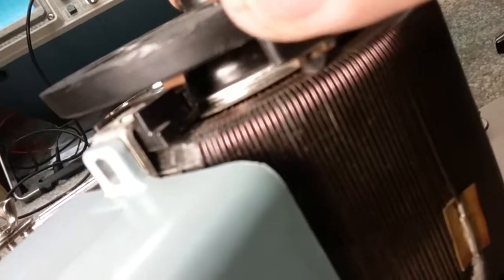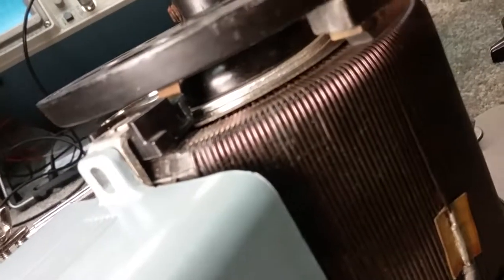This contact was bottomed out. The screws here needed to be reset, so I had to drop the plate. I dropped the plate down a little bit, and you got plenty of contact left. You can see the contact in there — let me put the light back down. There you go, see, the contact is hardly even worn. It was just beginning to come up off of the coil, and now it's got good pressure. It's back where it belongs.